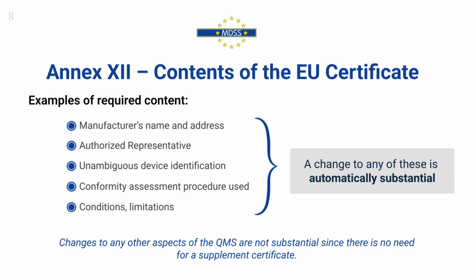While the word minimum is used, the Annex sets forth a comprehensive list of certificate elements. Here are just a few examples of elements that are required on the certificate. When any of this changes, the manufacturer is obligated to inform the notified body. For example, a change in the manufacturer's name or address. This directly affects the identification of the legal entity holding the certificate. A change in the authorized representative. If the address of the representative is listed on the certificate, any modification will also lead to a supplement to the certificate. A change in the devices or device range covered.